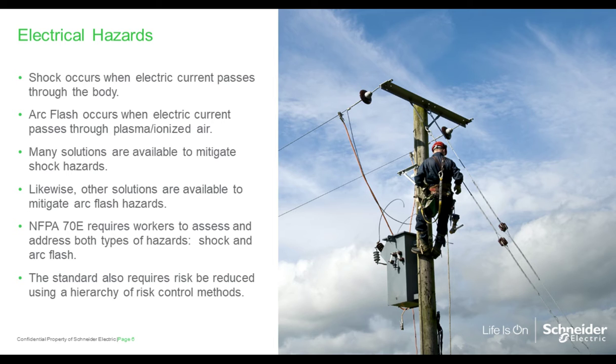Unfortunately, electric shock is relatively common. According to NFPA 70E Annex K, there are approximately 30,000 non-fatal shock accidents per year. While that may be what is documented, I believe that number is far too low, because nearly everyone I know has experienced an electrical shock at one time or another, and many of us have been shocked more than once. So I wouldn't be surprised to find out that number is actually 1 or 2 orders of magnitude higher.